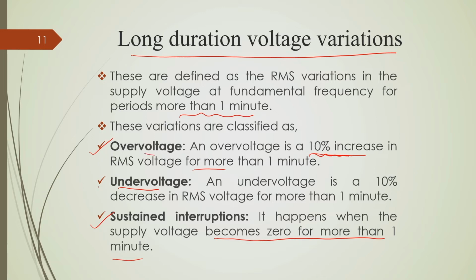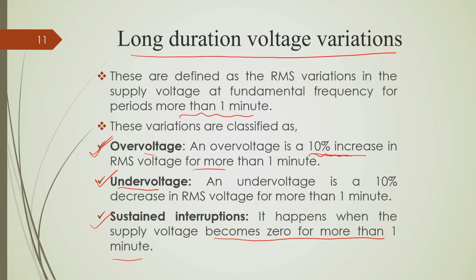So, under voltage is the dip of the RMS value of the supply voltage for more than 5 to 10%. Okay. 5 to 10% variation of voltage is acceptable. Similarly, over voltage is an increase of the RMS value of the supply voltage for more than 1 minute, by more than 10% of the supply voltage.